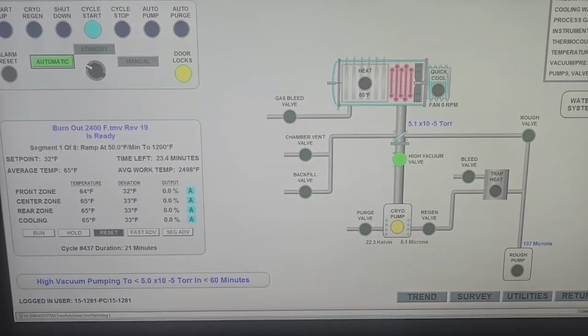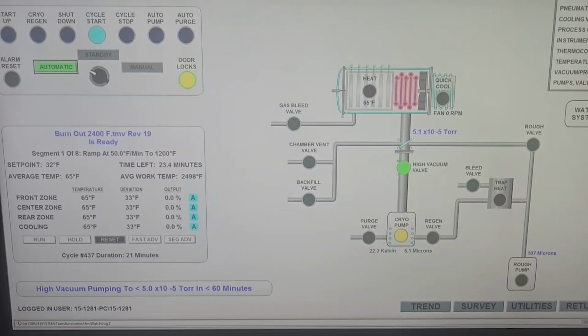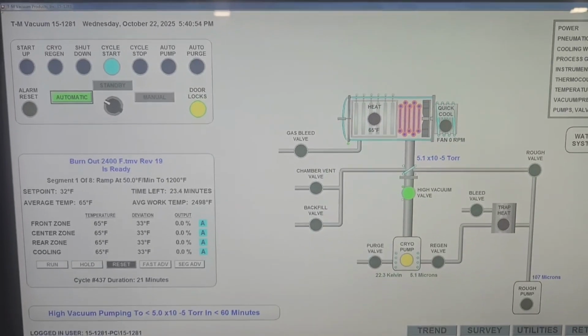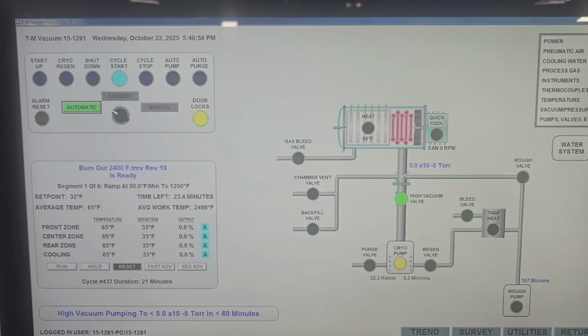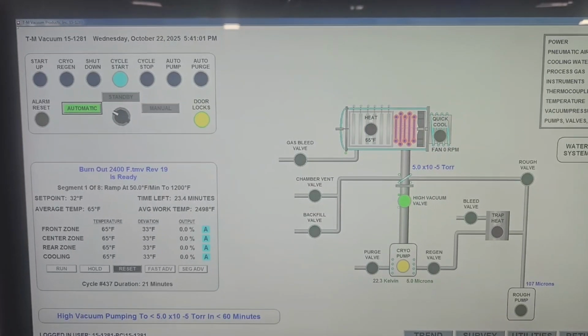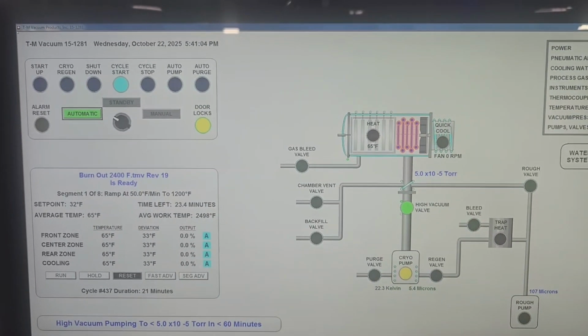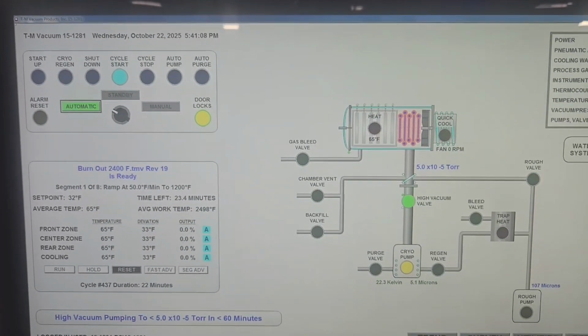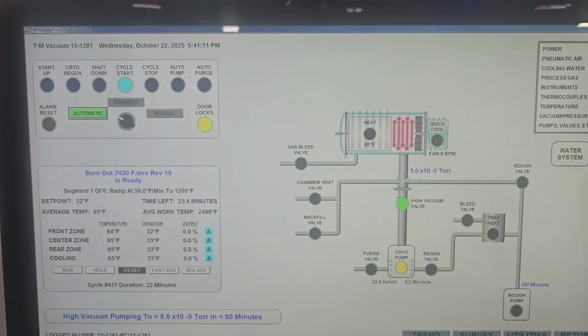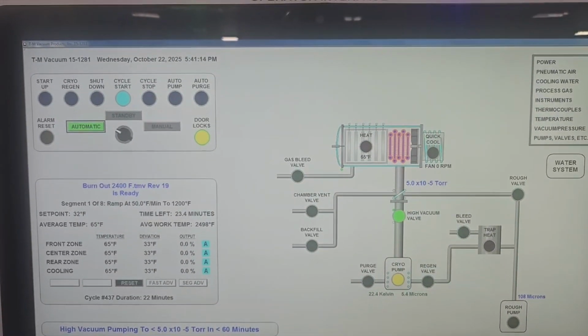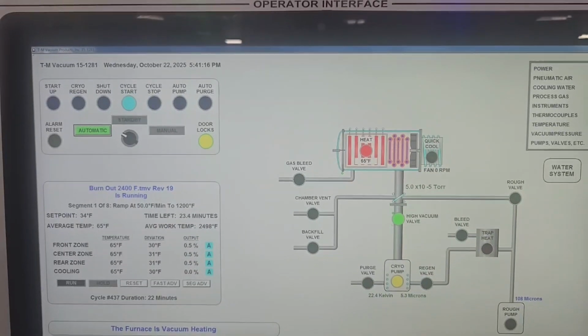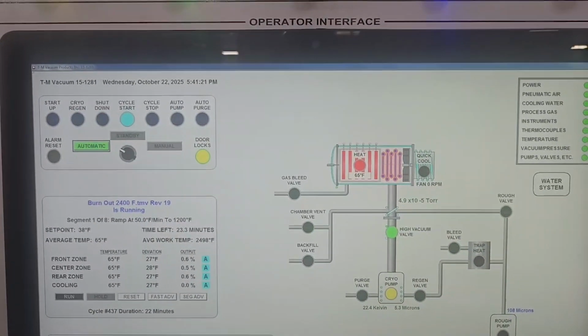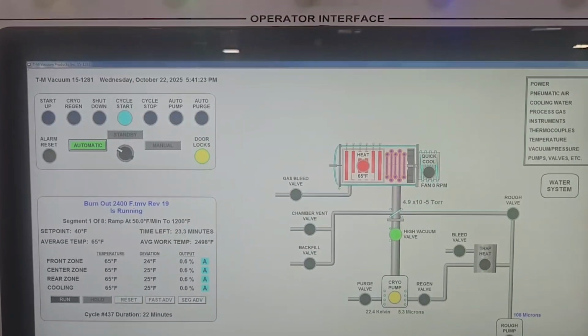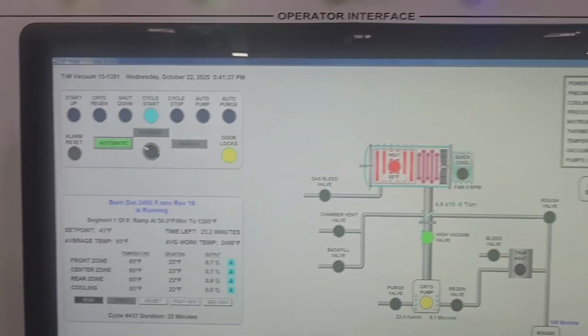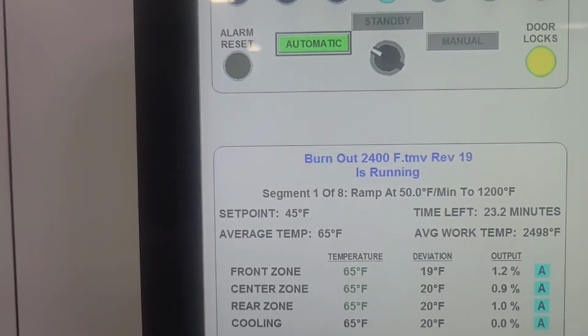The torr rating is at 5.1 times 10 to the -5 torr. The unit is pumping down until it gets to 5.0 times 10 to the -5. It will then apply the heat in the chamber. Okay, the heat's being applied. It's ramping to 1200 degrees Fahrenheit, 50 degrees per minute.